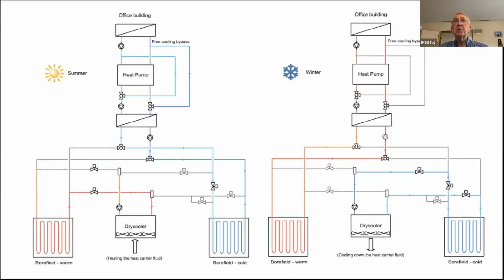So here's what's going on with this example. The dry cooler doesn't have any way to feed into the heat pump in this design, but the dry cooler plays a very useful role. It's used in the extreme temperature conditions of summer and winter to do preconditioning of what they call the bore field. Bore field being a bunch of boreholes with plastic pipe embedded in them. So you'll see here on the left, the dry cooler is being used only to precondition the left-hand bore field. It's got red because that's supposed to indicate hot. At the same time, this is being a very hot summer afternoon.